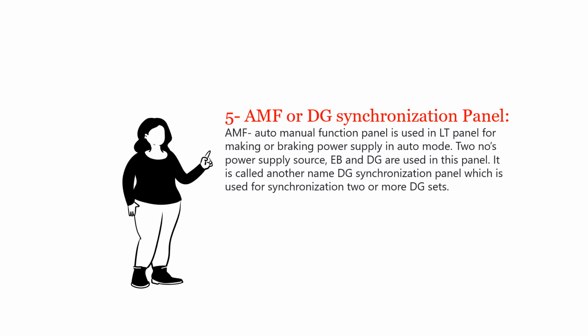AMF or DG synchronization panel. AMF means auto main failure. The panel is used in LT panel for making or breaking power supply in auto mode. Two power supply sources, EB and DG, are used in this panel. It is also called a synchronization panel, which is used for synchronizing two or more DG sets.